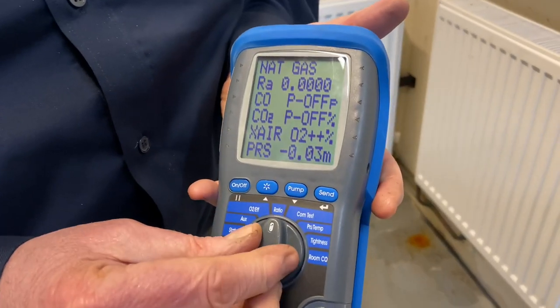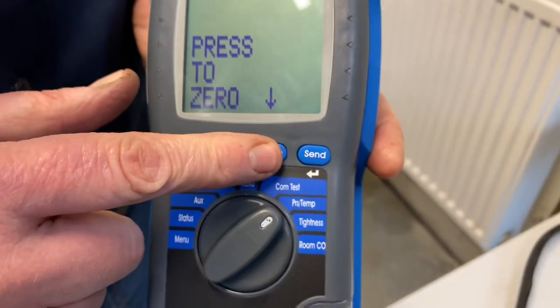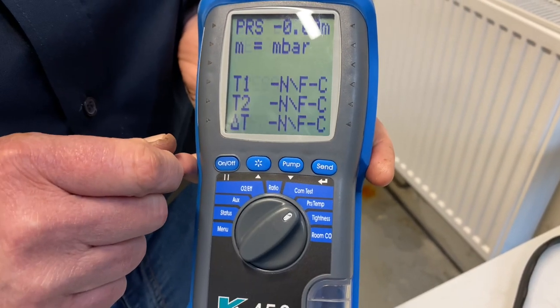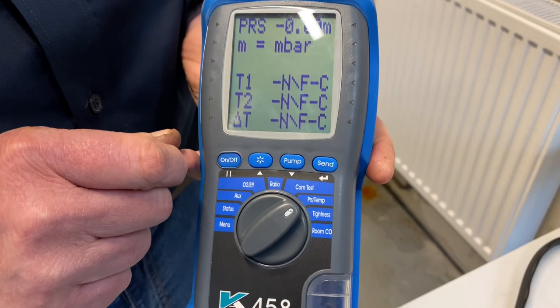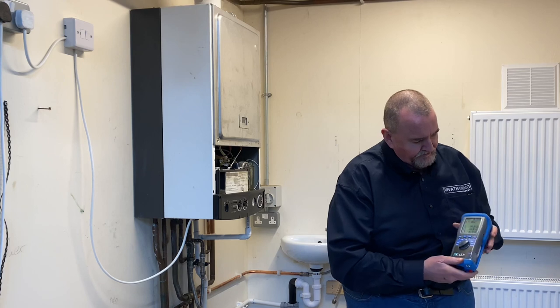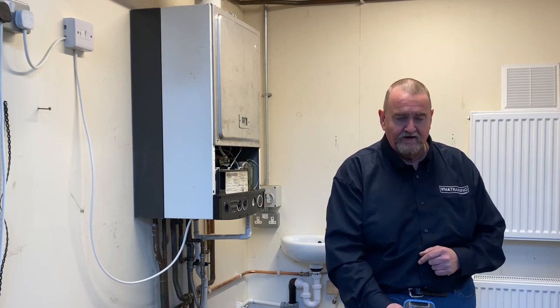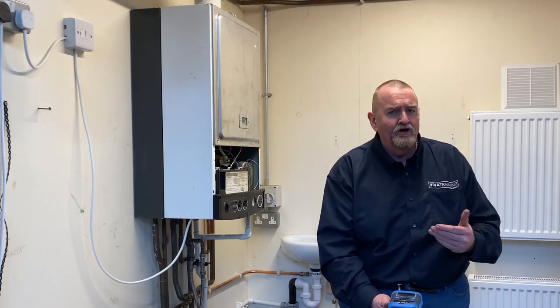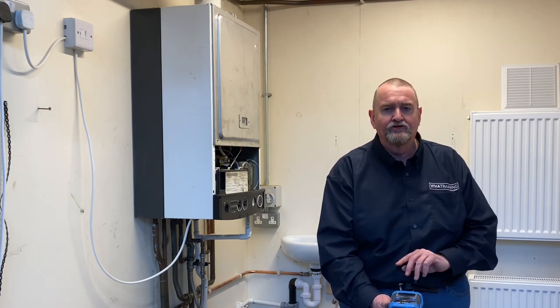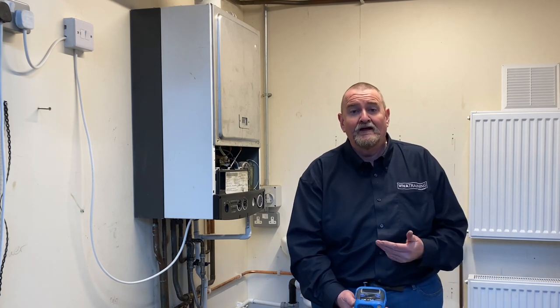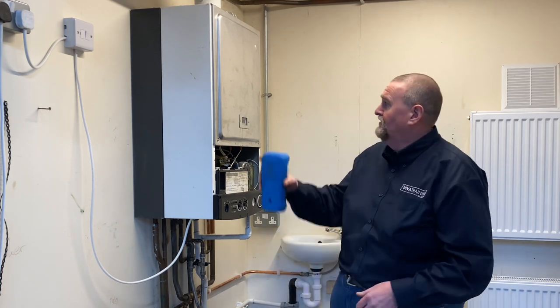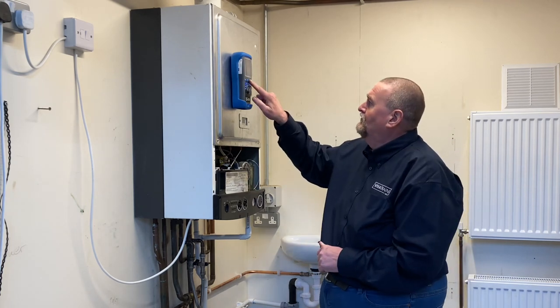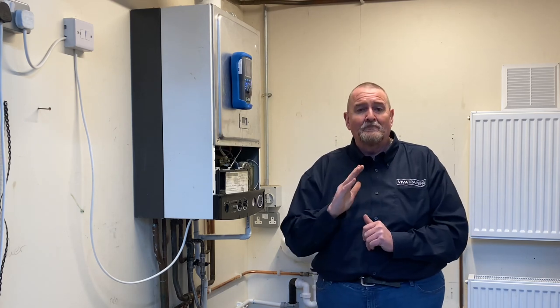We're going to move on now to using the analyzer in manometer mode, so I don't need the probes anymore. Going into pressures and temperatures, it's asking me to zero. A little trick with the Kane analyzer: if you zero it in the vertical plane and then put it into the horizontal plane, it will change the figure but only very slightly - about 0.02 of a millibar. If you're doing differential pressures you'd need to zero it again. I always use the zero button just before use to make sure I'm bang on zero.